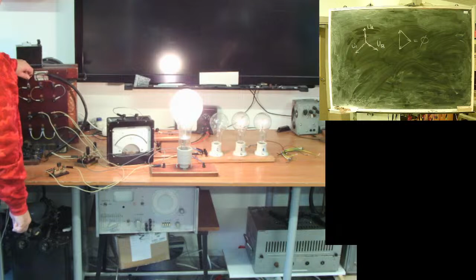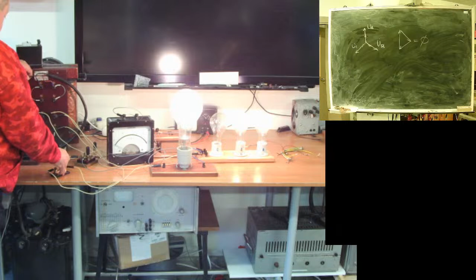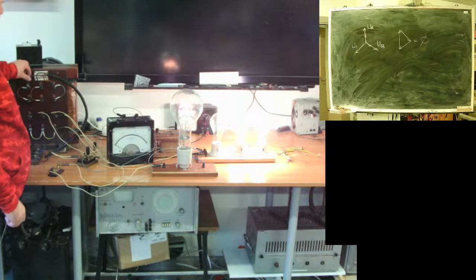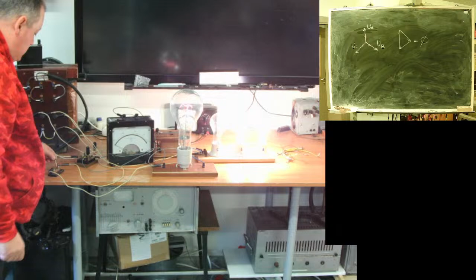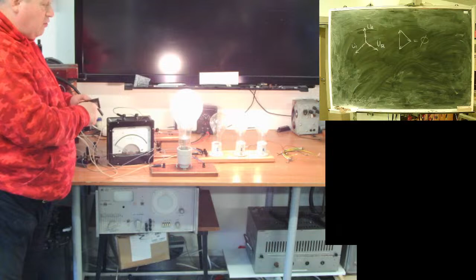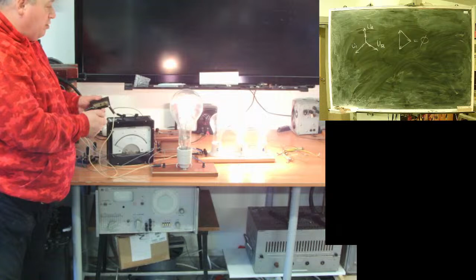More brutal. I disconnected A phase with the ground wire, C phase disconnected without the ground wire. In symmetrical mode, where all loads are equal, the ground wire is redundant. But if loads are not symmetrical, you can see what happens.